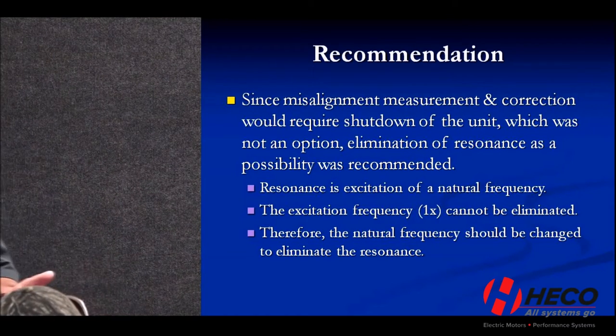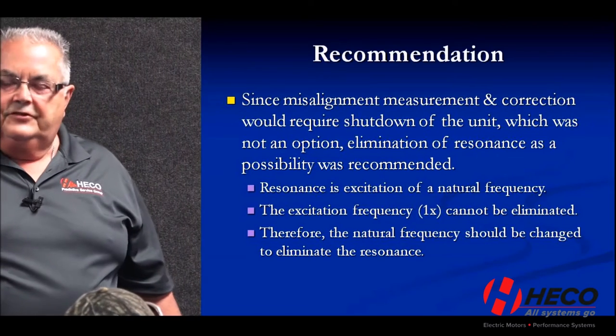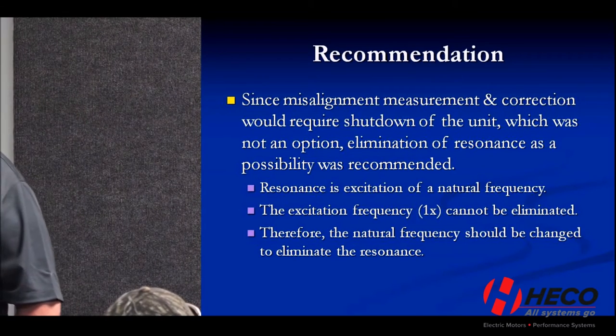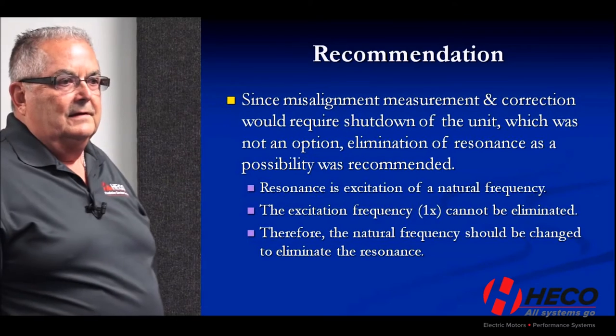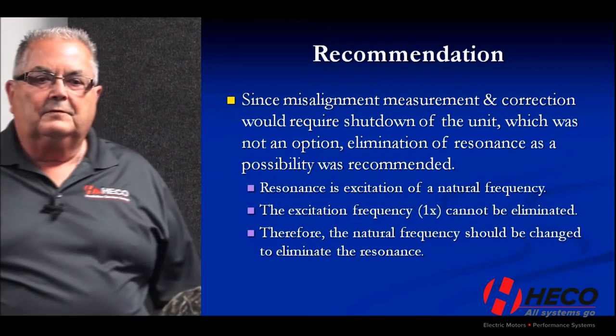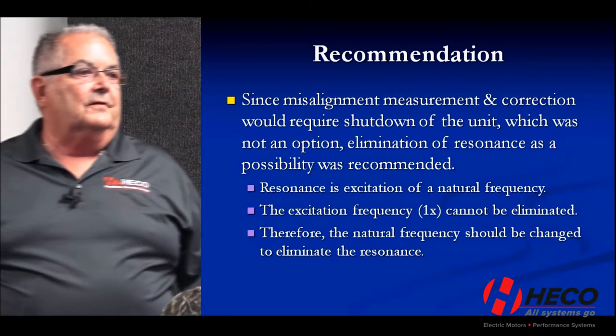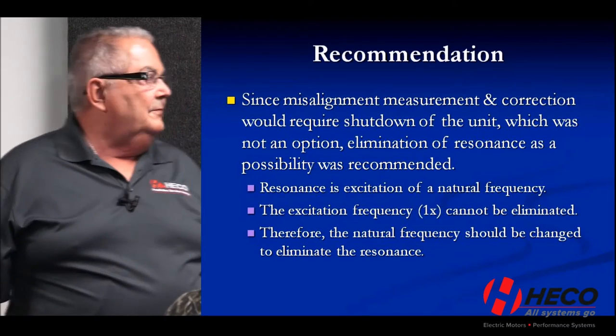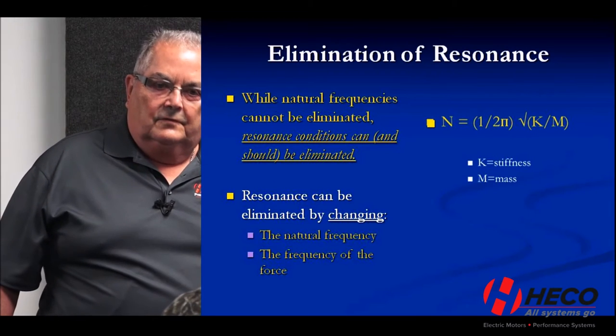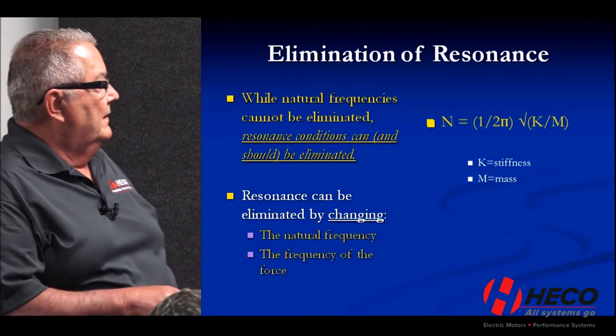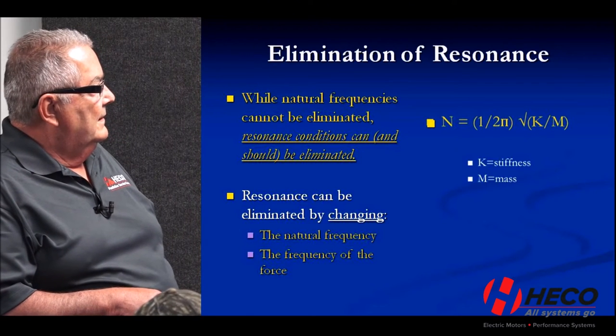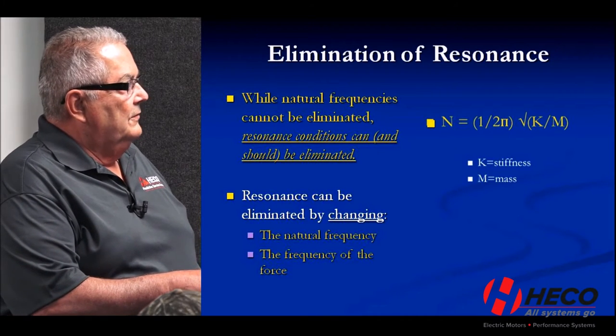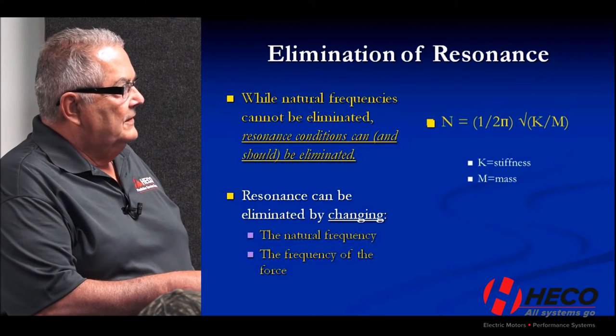To check if it's a resonance: if you have a resonance condition, the way you fix it is to change something. There are three things you can change. One — change the speed — but this isn't on a variable frequency drive, so that's not an option. The other two are stiffness and mass. The natural frequency formula is: one over two-pi times the square root of stiffness divided by mass — fn = (1/2π)√(k/m).